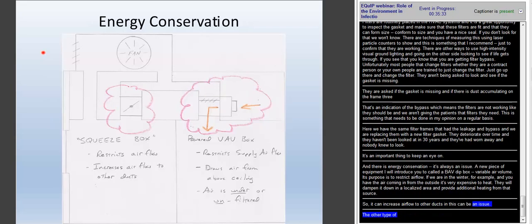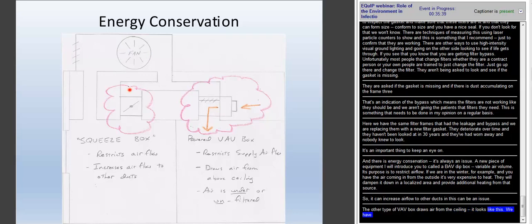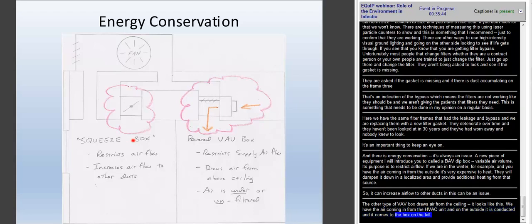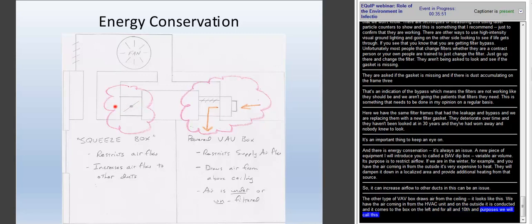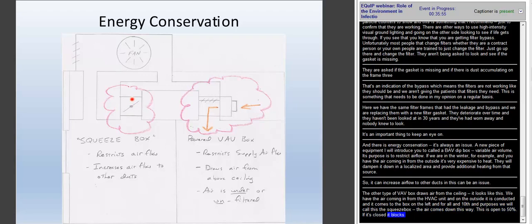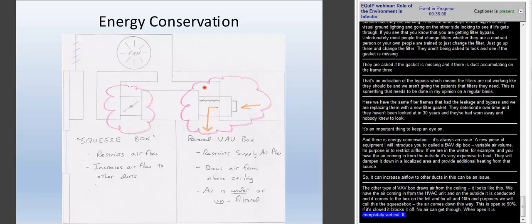The other type of VAV box draws air that's either less filtered or unfiltered from above the ceiling, and they look like this. We have the air coming in from the HVAC unit from the outside. It's ducted, and it comes down here to the box on the left that we'll call, for all intents and purposes, a squeeze box. The air is supposed to come down this way. This is open at 50%. If it's closed, it completely blocks it off, and no air can get through. If it's open, it's completely vertical. And all it does is restrict airflow, but when you do that, it increases the airflow to other ducts, which could be an issue and could change pressurization in other spaces.